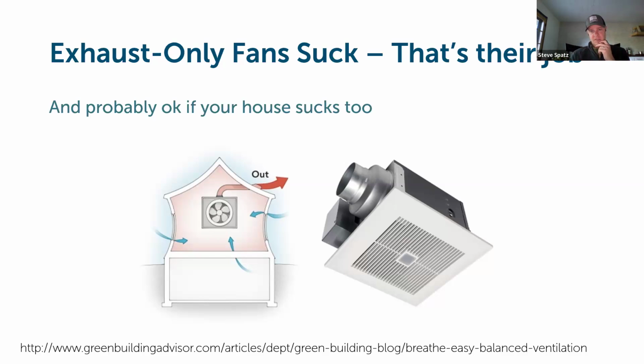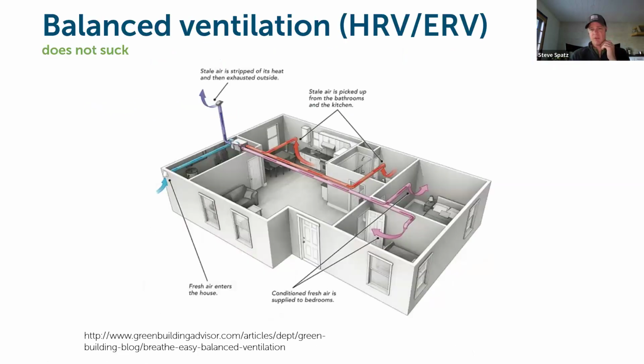In the current code up until July 1st, you could prescriptively meet the whole house mechanical ventilation requirement by putting one bath fan that's rated to move 100 CFM in one bathroom of a 3,000 square foot house, with 4 occupants, that's on a timer to come on and run during the day and be considered that you have a whole house ventilation system. But practically speaking, that one bath fan is not going to be providing ventilation air throughout the building. So this is what I was getting at earlier when I said we're just kind of at a point where whole house distributed ventilation has been more of a necessity for a while now. And we're now getting to the point where this is what the expectation is to be met.